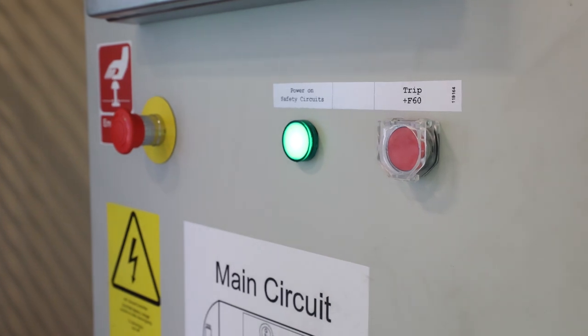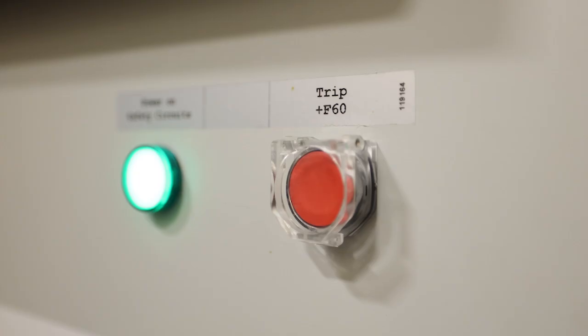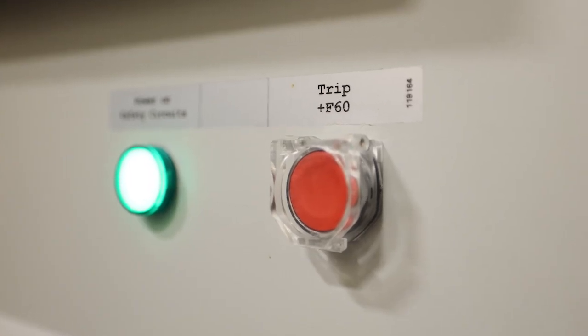They'll be able to isolate the switchgear from further up the circuit, so no one is in the vicinity when it's de-energized. If there's an issue with the turbine itself and you need to remove the electricity supply to it in an emergency, you can activate the emergency trip or stop. So activate this if there's an issue with the turbine, but not if there's an issue with the switchgear itself. Definitely not. We can't predict how the switchgear would react if it was tripped, so if there's a problem with it, leave the turbine and alert the control room.